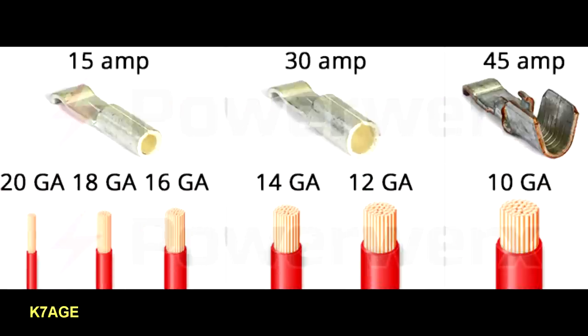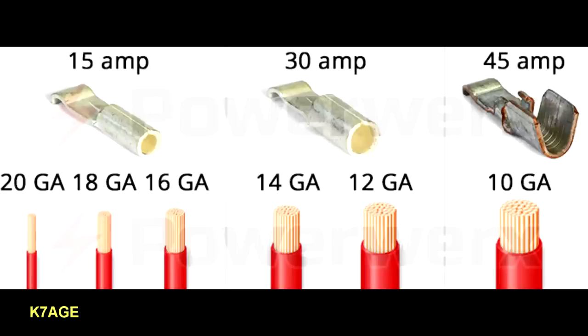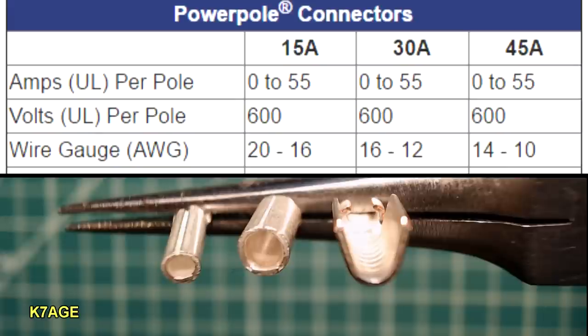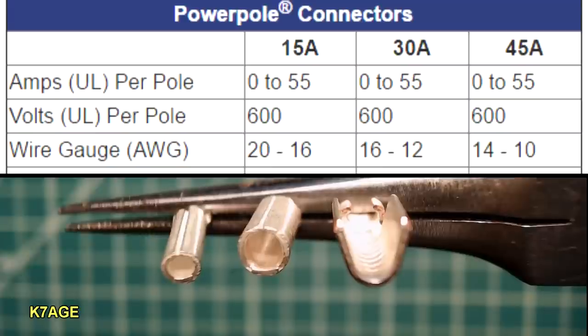The connector body will accept a 15, a 30, or a 45 amp connector pin. Now, all the pins handle 45 amps, but what's different here is the gauge of wire that the pins will accept. We have a small, a medium, and a large. So the 15 amp will accept a 20 through 16 gauge wire. A 30 amp will accept a 16 gauge through a 12 gauge wire. And a 45 amp will accept a 14 through 10 gauge wire. Now, you can mate a 45 to a 15, so we don't have to select the pin based on the current size. We select the pin based on the wire size.